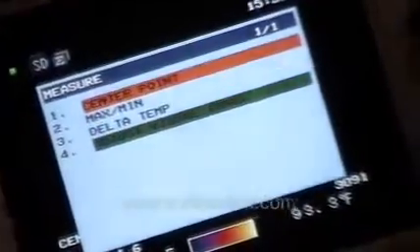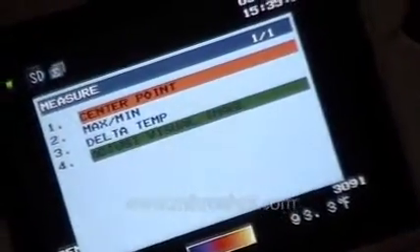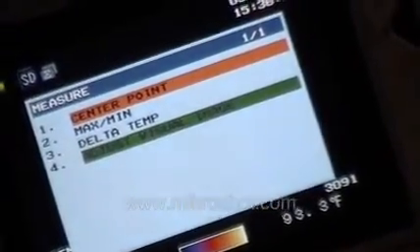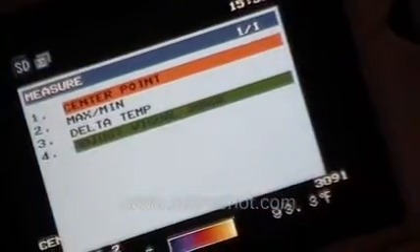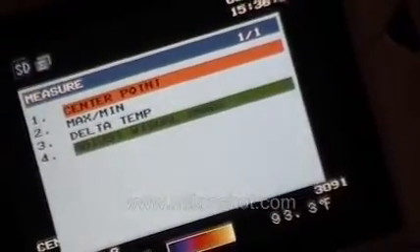In the measure menu, we're able to display the center point temperature. We can also display the roving minimum or maximum temperature and whether or not we want to display the delta temperature between the center point and the user adjustable moving cursor.